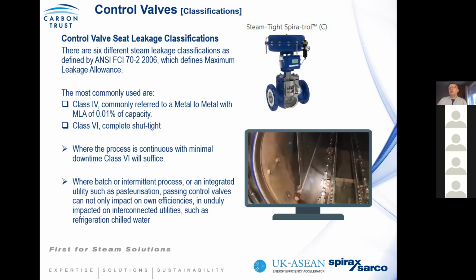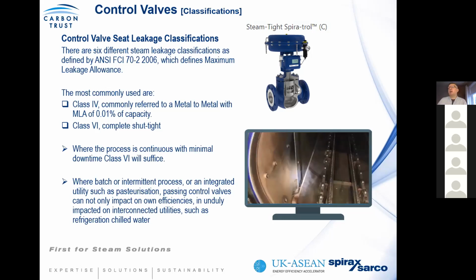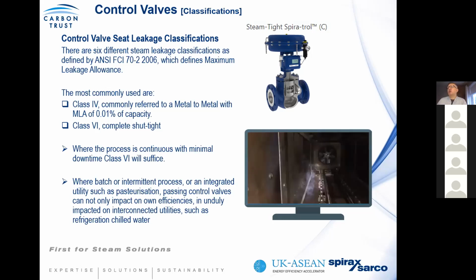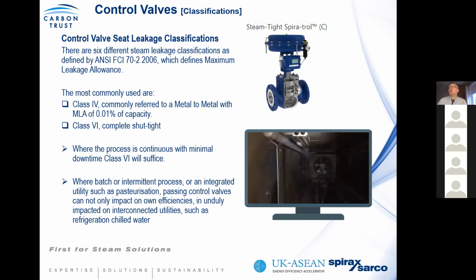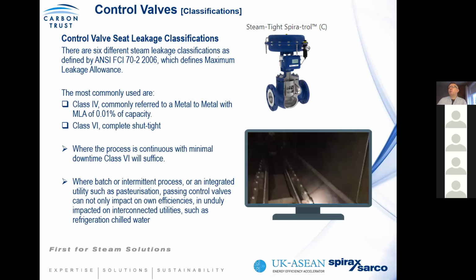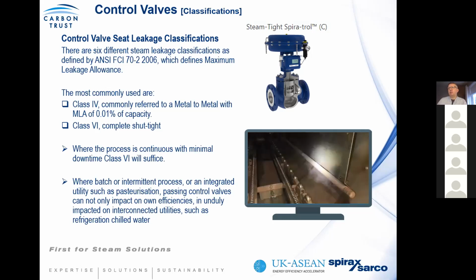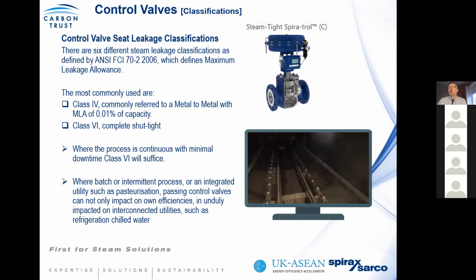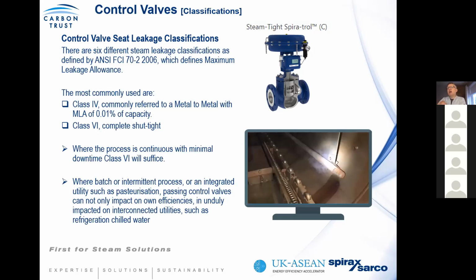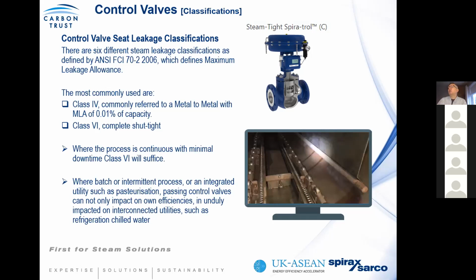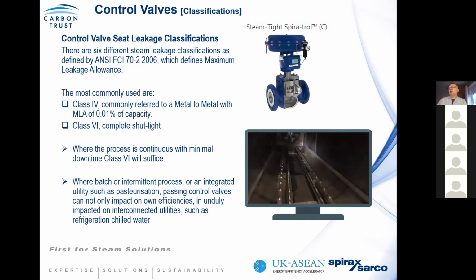So it's important to understand that you should be looking at what we call life cycle costs. And what this means is that you don't look at the cheapest valve, you put in a valve designed for the application. So if it's on, off, or intermittent, you should have a class 6 type valve. If it's a continuous operation, a class 4 will do, because you will always be controlling a steam supply.